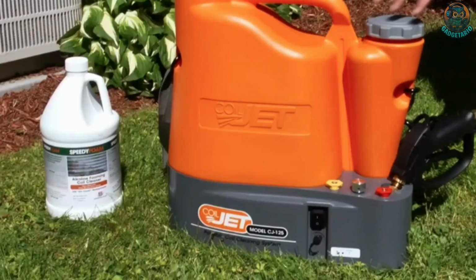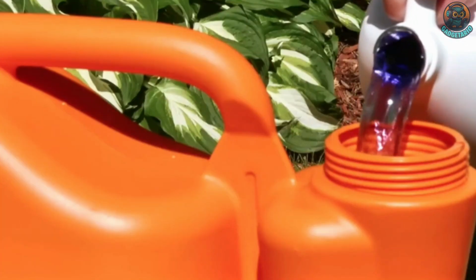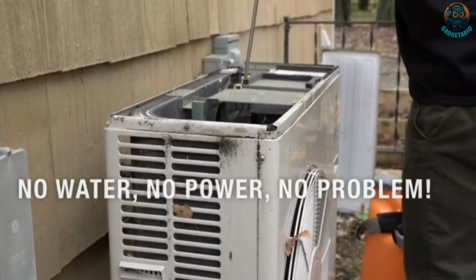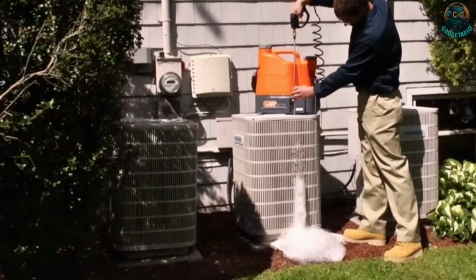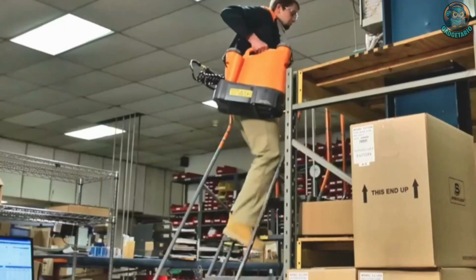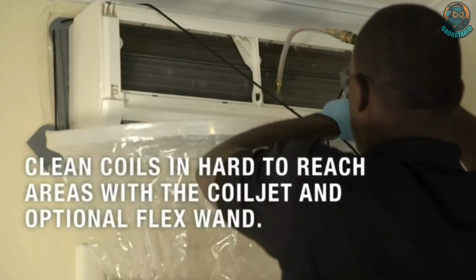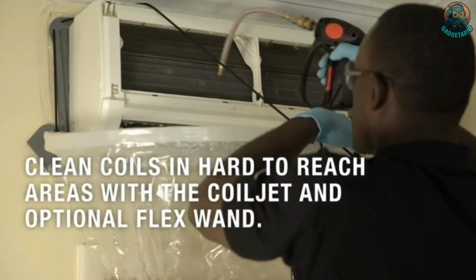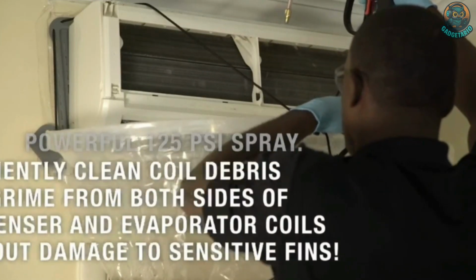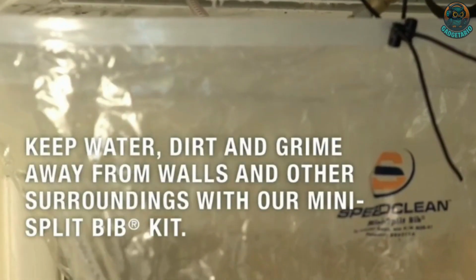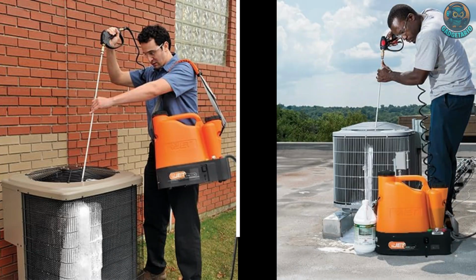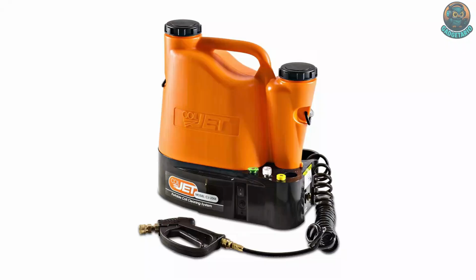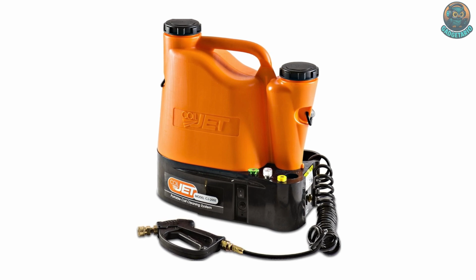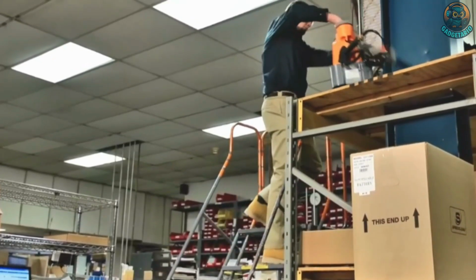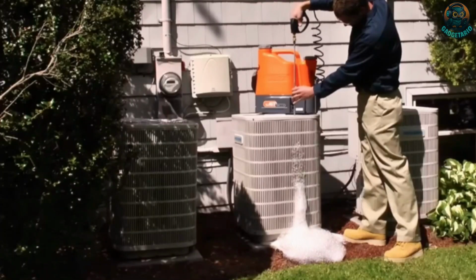AC Coil Cleaner. The Speed Clean Coil Jet CJ200E portable electric coil cleaner is a professional-grade cleaning system designed for efficient and safe coil maintenance. Ideal for HVAC and refrigeration coils, it delivers up to 220 psi of adjustable spray pressure, strong enough to remove dirt and grime without damaging delicate fins. It features a 3.375-gallon onboard water tank and a 1.75-quart chemical reservoir, giving users the flexibility to clean units without needing a water connection, perfect for rooftops or hard-to-reach areas. The electric-powered unit, 110V, is portable, comes with a 15-foot power cord, and includes a quick disconnect spray gun with interchangeable nozzles for various cleaning angles. A shoulder strap and compact design make it easy to carry, even when full. Weighing about 22 pounds dry.